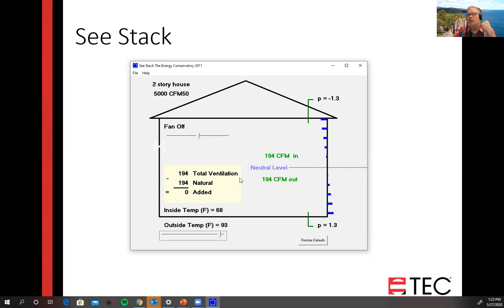That upstairs system is going to be working harder because of this warm air coming into the house. And the downstairs system kind of gets a pass because the air that's entering the lower floor has already been conditioned from upstairs, and then you leak some conditioned air out. So that means that design load, at least on a day when there's no wind, is mostly going to affect the upstairs system. But we'll talk later about the effect of wind.